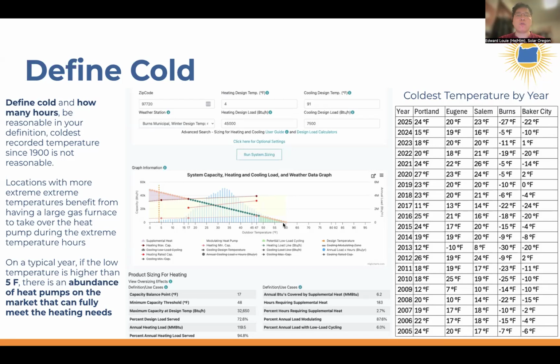So when you have more extreme extremes, it becomes harder for one heat pump to be able to meet both the extremely mild days and also the extremely cold days. So a compromise could be that dual fuel is the right compromise, so that you can size a heat pump so that it's not so big, so that there are still very few hours and few days where the heat pump needs to cycle on and off because the load is so low. But then you still have a large enough furnace to be able to cover when it ever gets to be minus 10 or minus 20 degrees outside. So, yeah, location is a major deciding factor of whether to go dual fuel or just straight heat pump only.